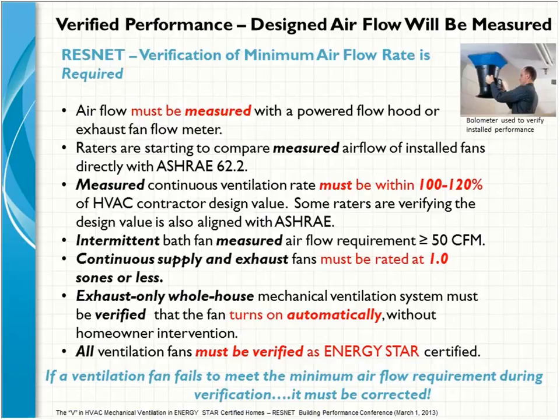So, I know that we have a bunch of raters here, so you folks know most of this information already. But when your homes are enrolled in any of the programs that we talked about, or built in states where the code requires it, it is important that all of the bathroom fans be measured. It used to be okay years ago to buy a 50 CFM bath fan that was rated at 50 CFM, install it, and you were good to go.